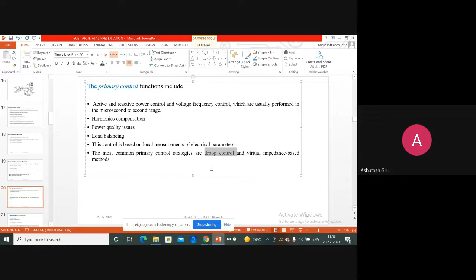The most common primary control strategies are droop control and virtual impedance based methods, right? Droop control means it is for the adjustment of frequency, voltage, reactive power, and frequency and active power, P and F, and V and Q. The secondary control performs functions such as energy management, economic dispatch, automatic generation control, spinning reserves, resynchronization, and fast load shedding, which usually take a time span longer than a second and involve communication. Basically, the secondary control works on communication, and secondary control can be implemented through either centralized or decentralized control. Model predictive control, somebody may have heard the name of model predictive control, multi-agent based control, droop control, probabilistic. There is something common between primary and secondary control.